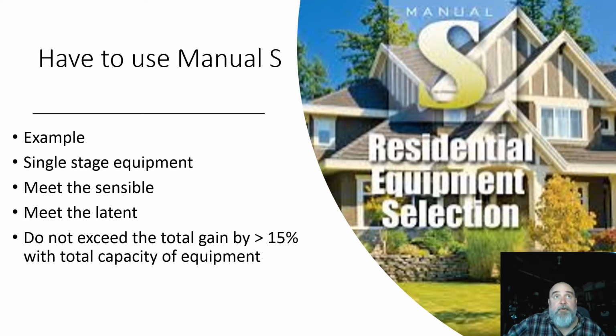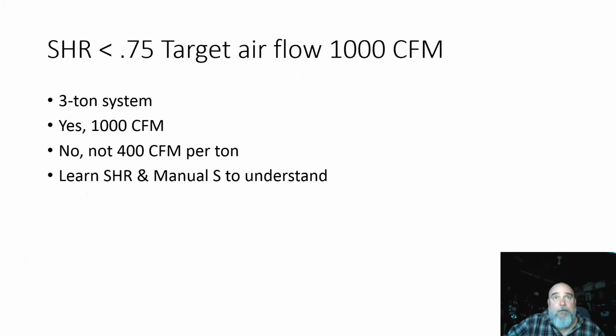In today's example, it's going to be single stage equipment. We did a load calculation and we selected equipment that met the sensible load, met the latent load, but did not exceed our total gain by more than 15%. And there's more guidance in Manual S that talks about two-stage equipment as well as variable volume equipment. But for this example, we're sticking with single-stage equipment.